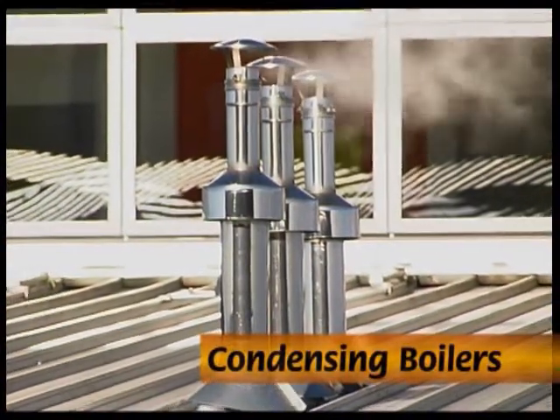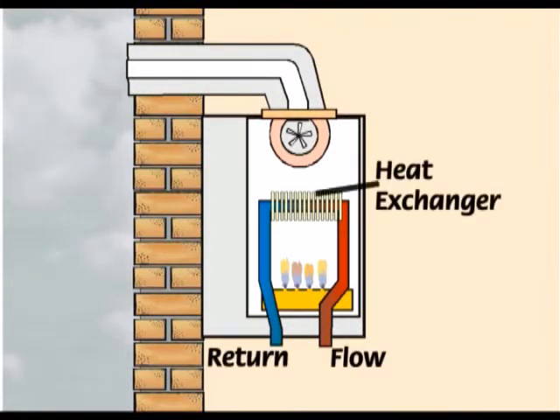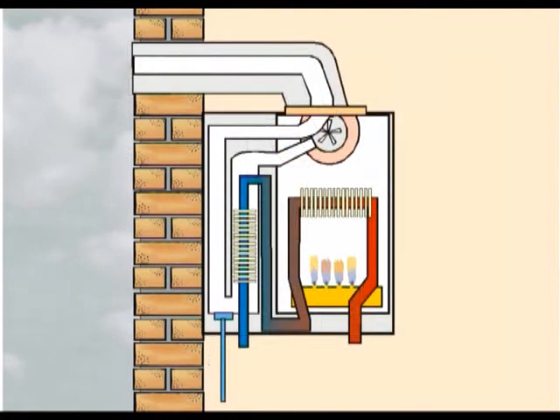In a modern oil or gas-fired boiler, about 70 to 80% of the fuel is converted into useful heat. The remainder is lost through the flue. The flue gases can be as hot as 250 degrees Celsius. In condensing boilers, more heat is extracted from the fuel. Their efficiency can exceed 90%. In fact, so much heat is extracted that the flue gases are only about 50 to 60 degrees.